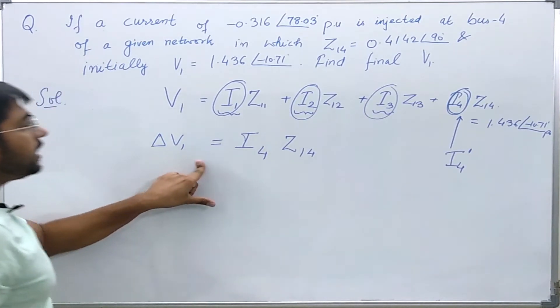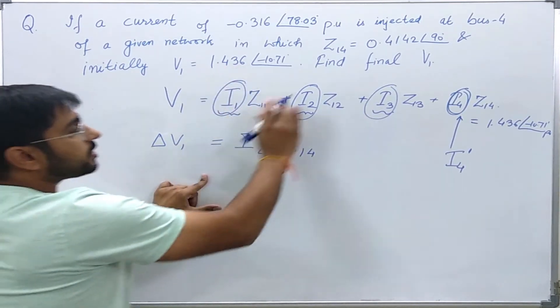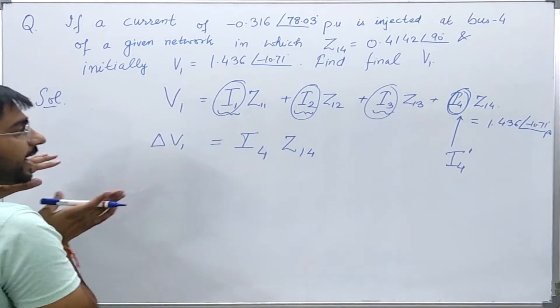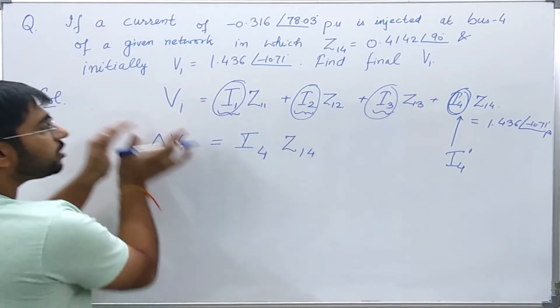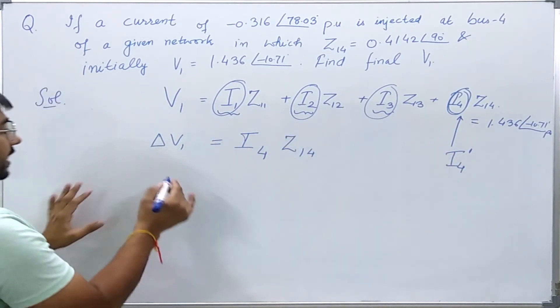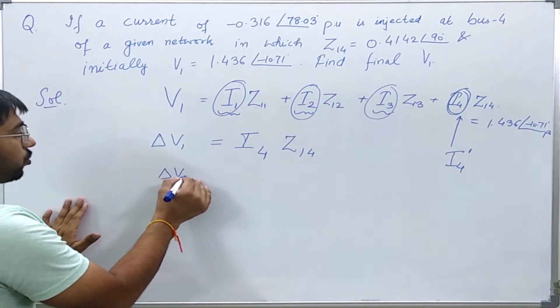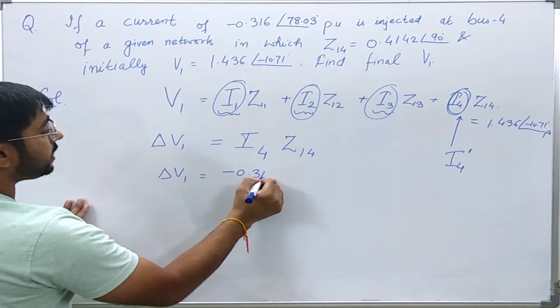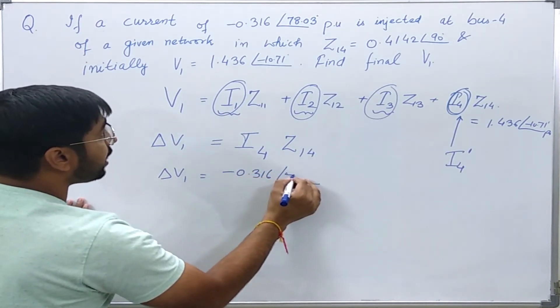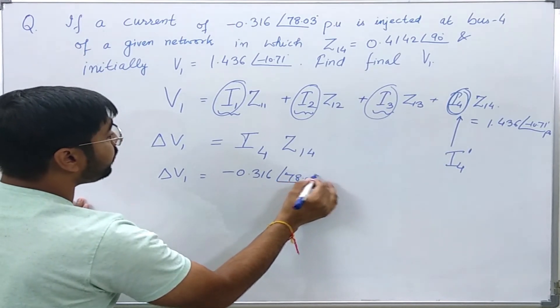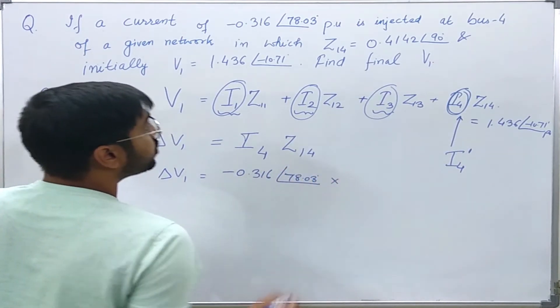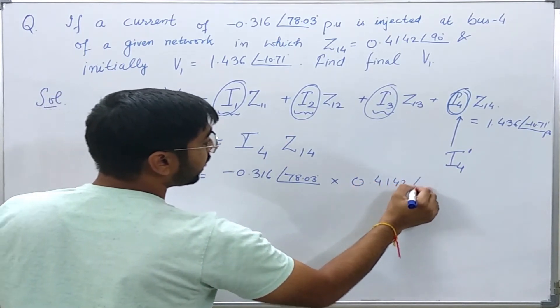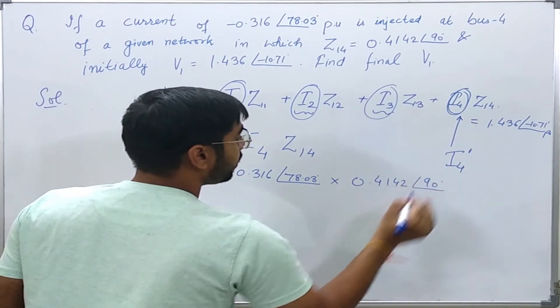So you see, if I deactivate these sources and just inject the given current source, then I will be able to find the change of voltage on bus 1 because of this current source. Delta V1 will come out to be minus 0.316 angle 78.03 degrees per unit into Z14, 0.4142 angle 90 degrees.